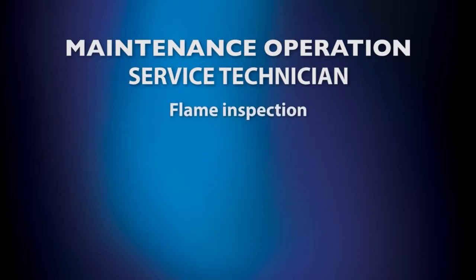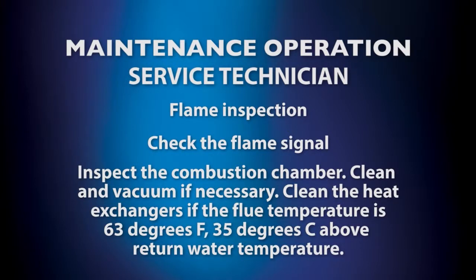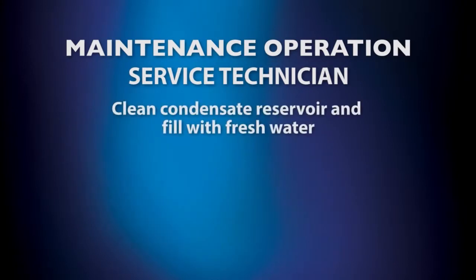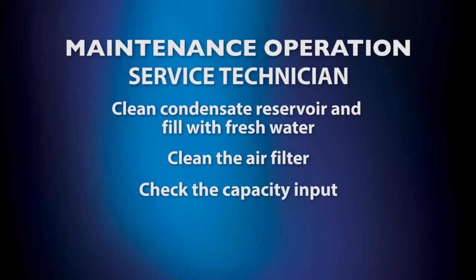Conduct a flame inspection. Check the flame signal. Inspect the combustion chamber. Clean and vacuum if necessary. Clean the heat exchangers if the flue temperature is 63 degrees Fahrenheit, 35 degrees Celsius above return water temperature. Clean condensate reservoir and fill with fresh water. Clean the air filter. Check the capacity input. Finally, check the relief valve.